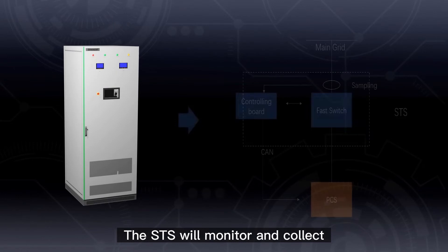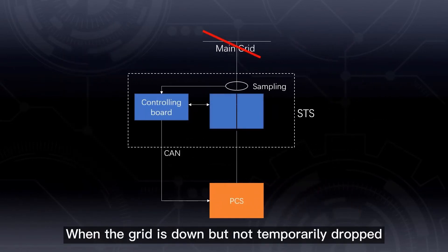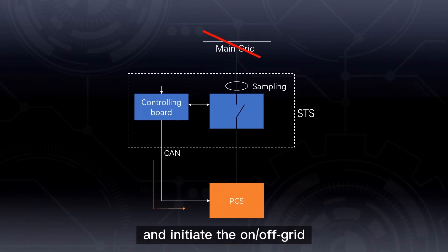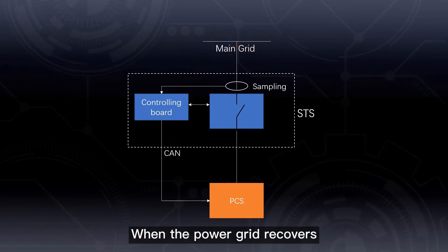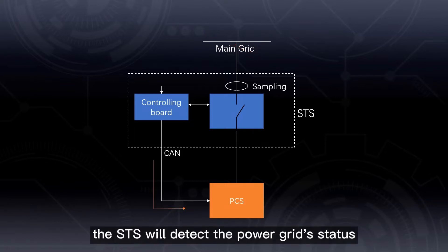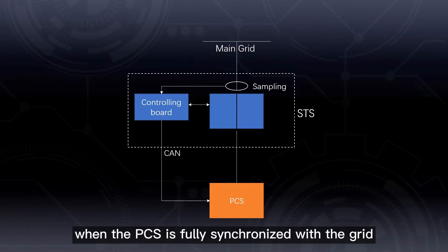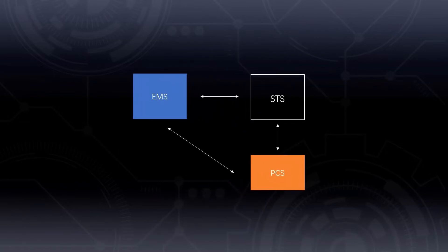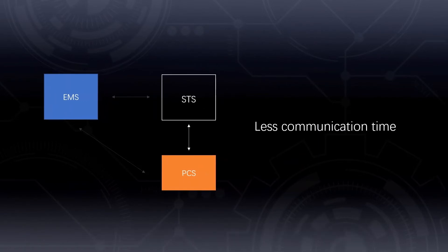So how does STS work? The STS will monitor and collect real-time grid data. When the grid is down — not temporarily dropped — the STS will disconnect the fast switch and initiate the on-grid and off-grid switching command to the PCS monitoring system. When the power grid recovers, the STS will detect the grid status and connect the fast switch once the PCS is fully synchronized with the grid, saving communication time among the normal transfer switch, PCS, and EMS.